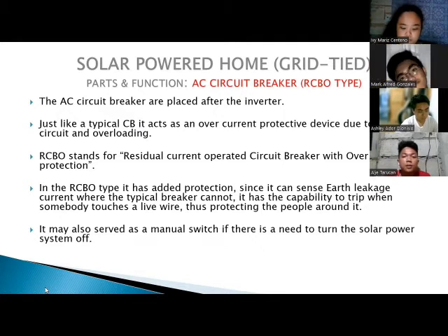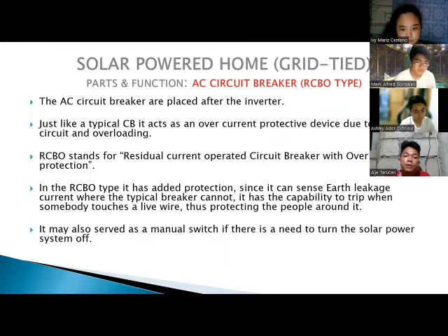Just like a typical circuit breaker, it acts as an overcurrent protective device against short circuit and overloading. The RCBO stands for residual current operated circuit breaker with overcurrent protection. In the RCBO types, it has added protections. Since it can sense earth leakage current where the typical breaker cannot, it has the capability to trip when somebody touches a live wire, thus protecting the people around it. It may also serve as a manual switch if there is a need to turn the solar power system off.